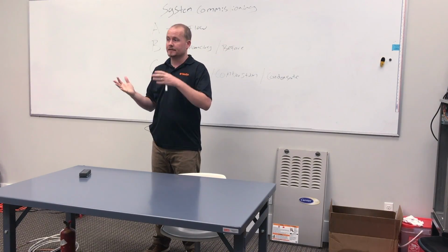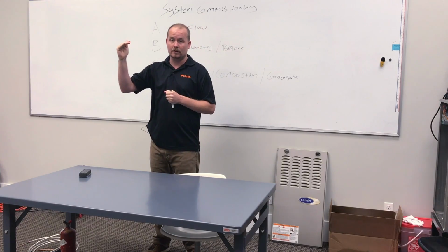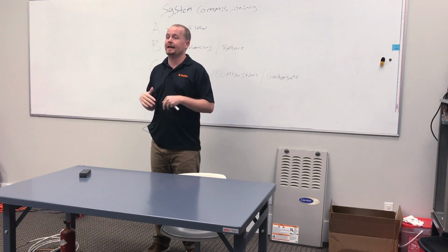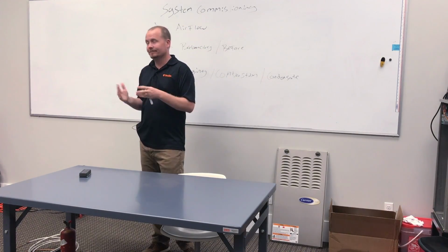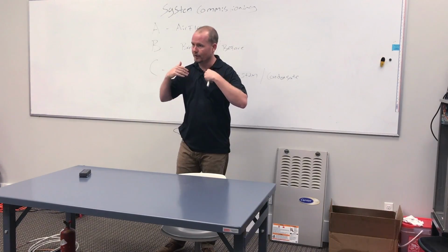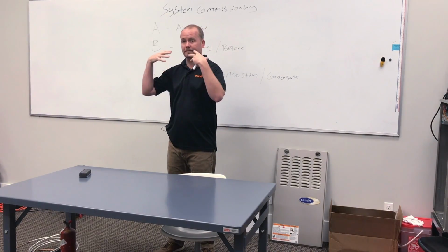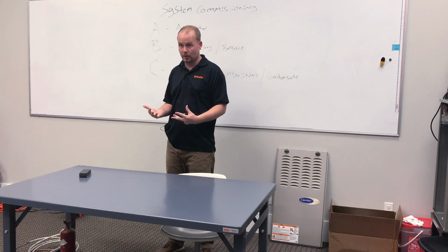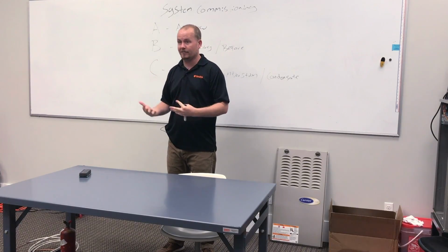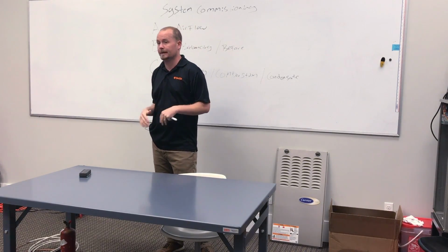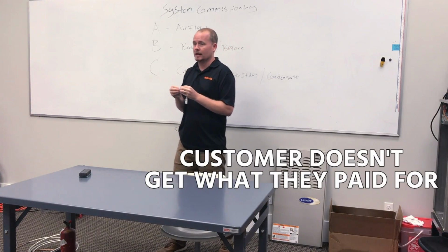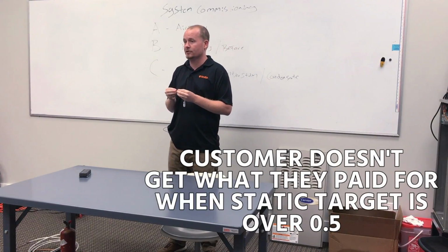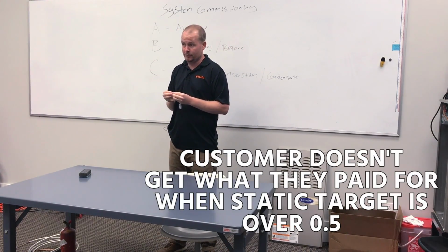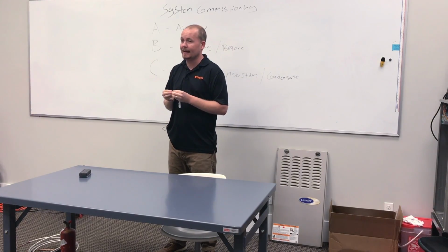Depending on the type of motor, it's going to change. Sometimes you'll take a hit in airflow, but at the very minimum, you're going to take a hit as far as capacity and efficiency. Not always capacity, but always efficiency. With higher static pressure, that blower is going to have to draw more amperage in order to do the same work, and it's going to put off more heat and use more energy. So the customer doesn't get what they pay for. Here's the point: the customer doesn't get what they pay for when the static pressure is over 0.5. They just don't.